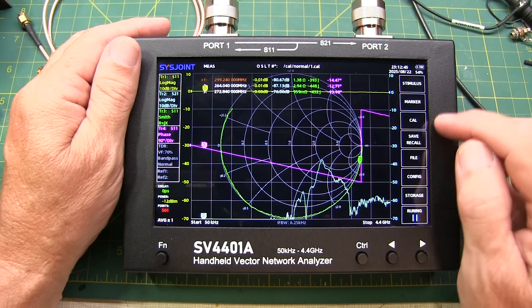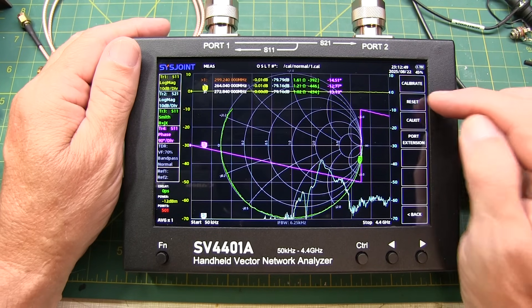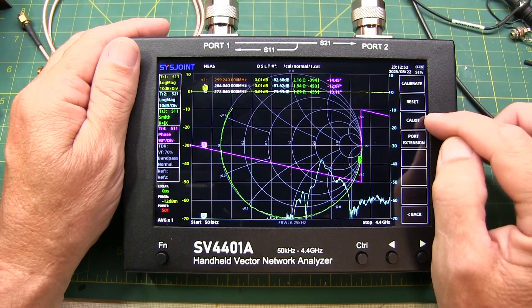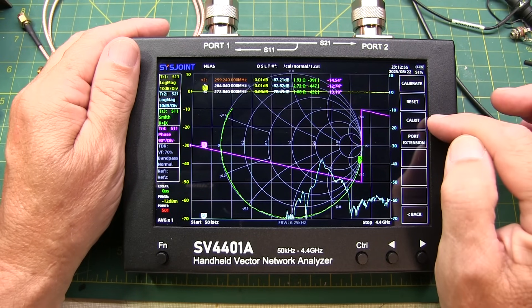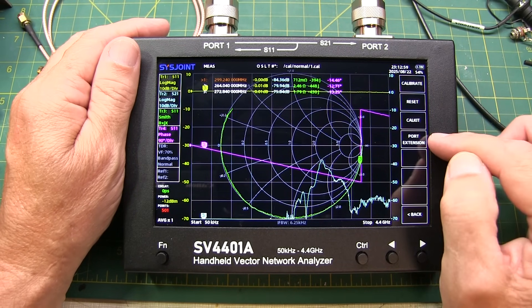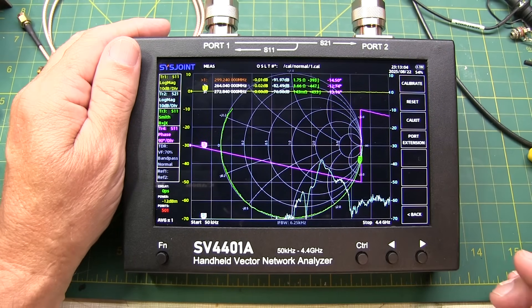Back at the top menu here, the CAL menu allows you to run through a calibration routine, reset it. You can even set the kind of second-order characteristics for high-performance calibration kits here as well, as well as setting port extensions to move the reference plane to your device under test.